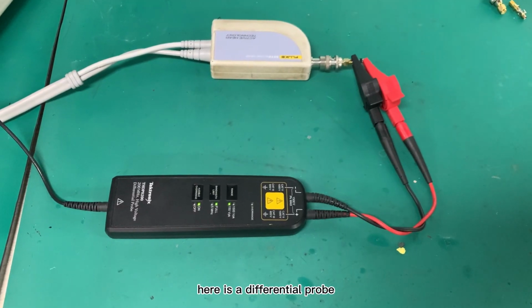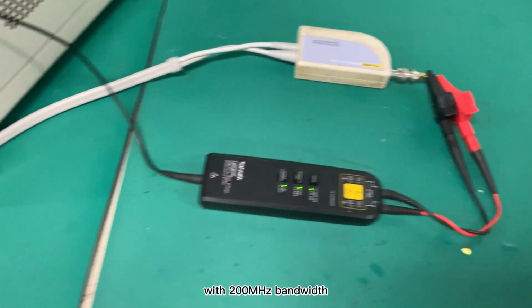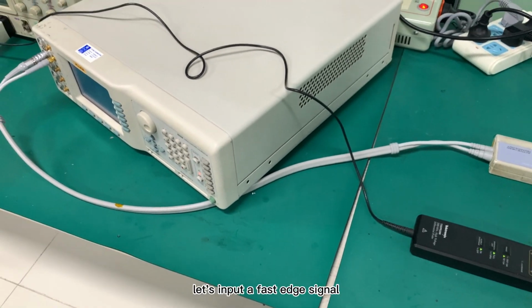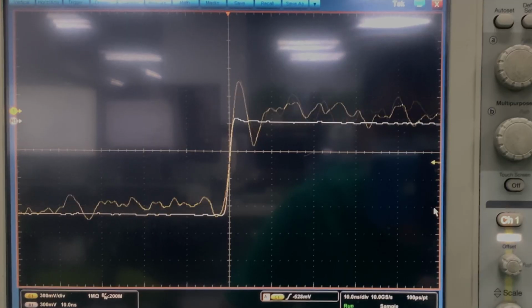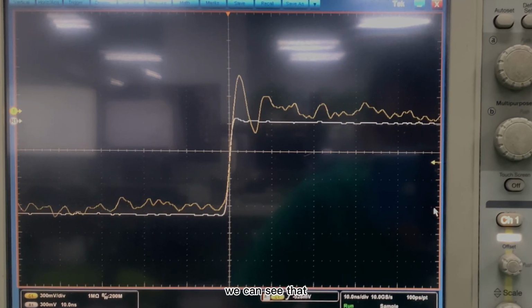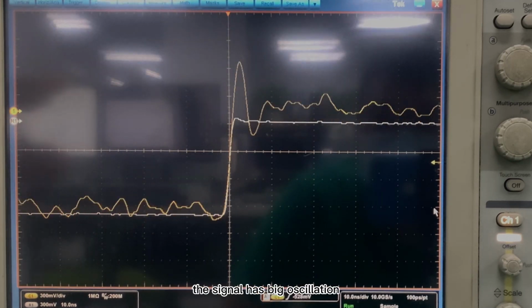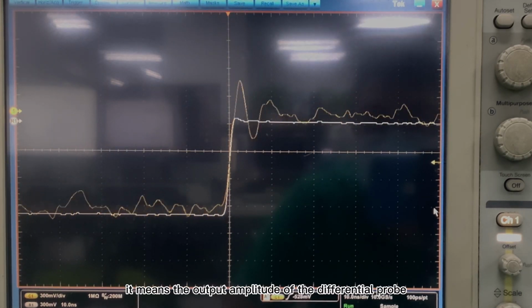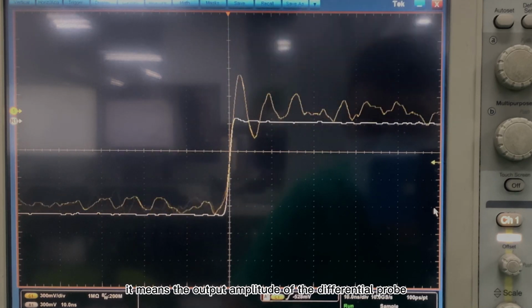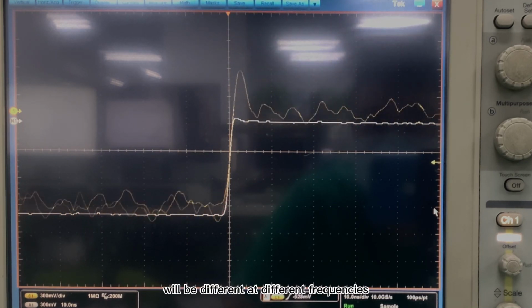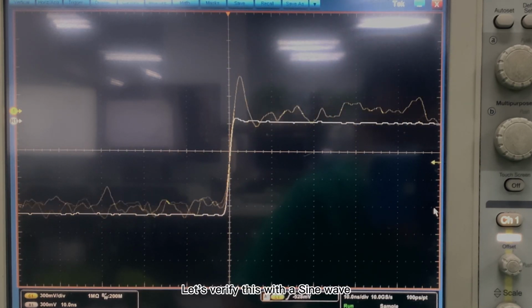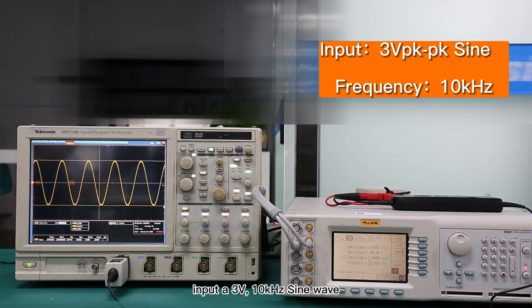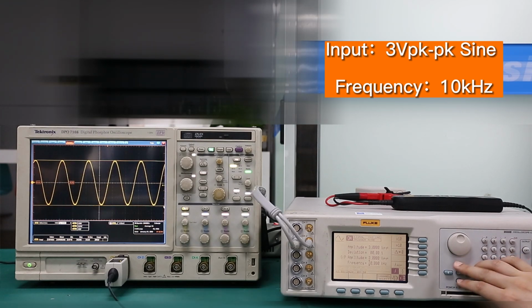Here is a differential probe with 200 MHz bandwidth. Let's input a fast edge signal to the differential probe. We can see that the signal has big oscillation. It means the output amplitude of the differential probe will be different at different frequencies. Let's verify this with a sine wave. Input a 3V, 10 kHz sine wave. Sweep from low frequency to high frequency. Check the differential probe's amplitude.